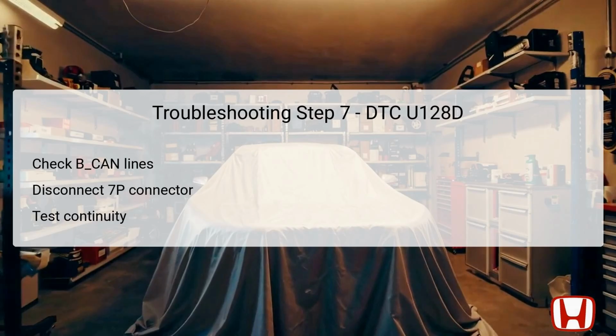For the 7th troubleshooting step, focus on verifying the B-CAN lines, which are critical for communication between the automatic lighting control unit and the gauge control module.